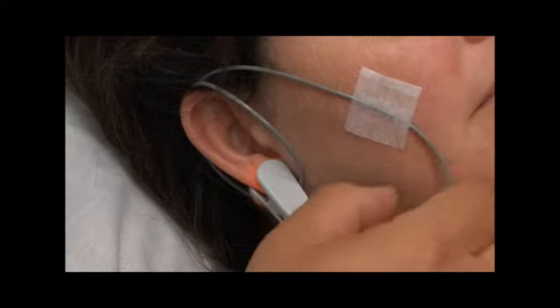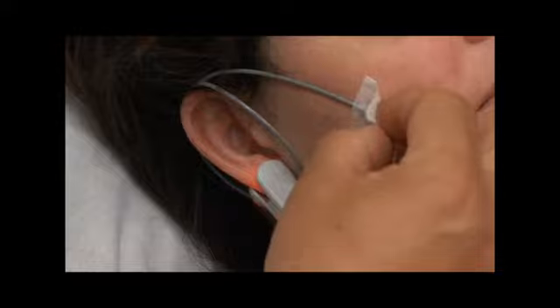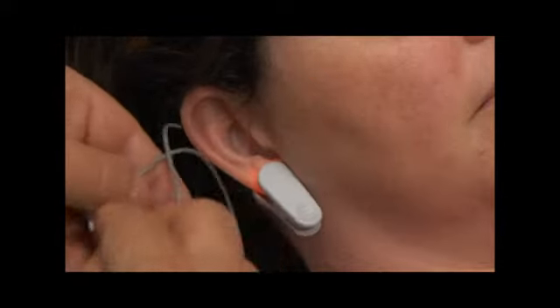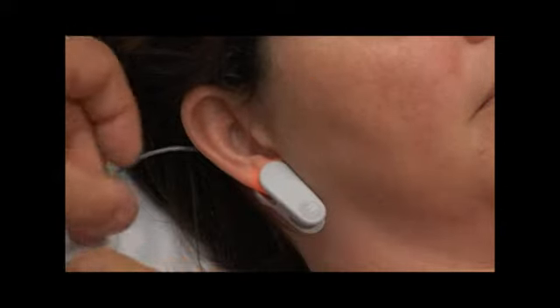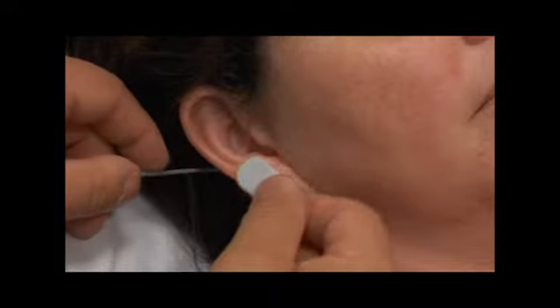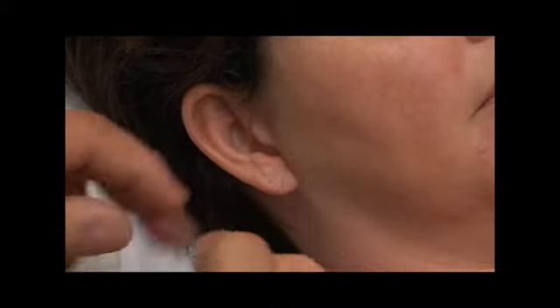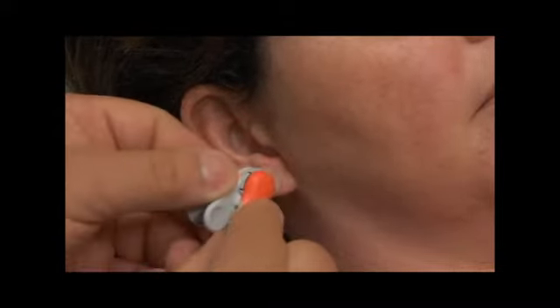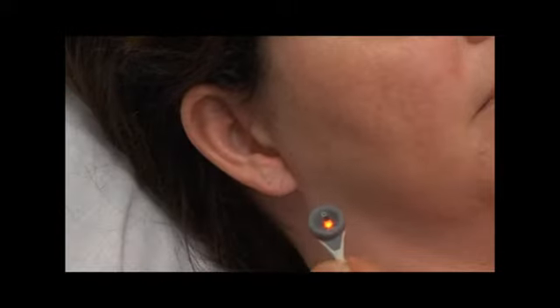Ear clip. Remove the adhesive tape from the sensor cable and unwind from the ear. Remove the ear clip carefully from the patient's earlobe, then detach the sensor carefully from the ear clip. Alternatively, you may also remove the sensor from the ear clip and leave the ear clip attached to the earlobe for further measurements.